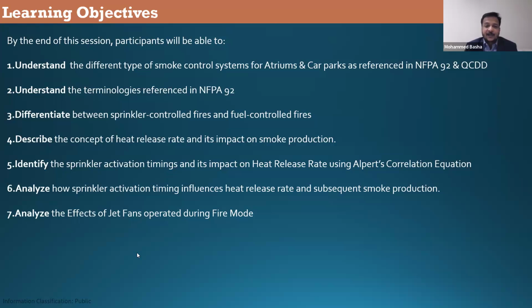Differentiate between sprinkler controlled fire and fuel controlled fire. Describe the concept of heat release rate and its impact on smoke production. Identify the sprinkler activation timing and its impact on heat release rate using the Alpert correlation equation, and how the sprinkler activation timing influences the heat release rate and subsequent smoke production. And analyze the effects of jet fans operated during the fire mode. So all these objectives lead to a final point: how to design a proper smoke exhaust system. To do this, we need to select the proper equipment, which is the fans, the capacities, and the number of outlets.